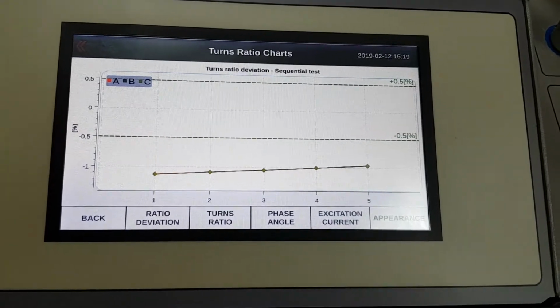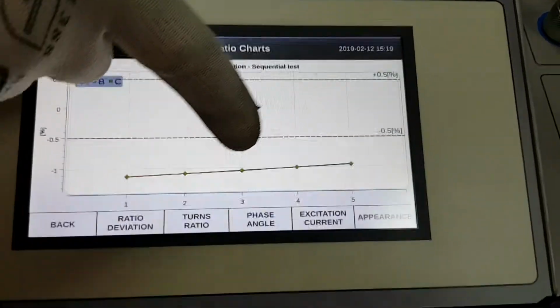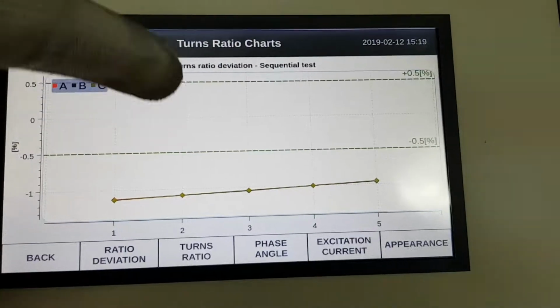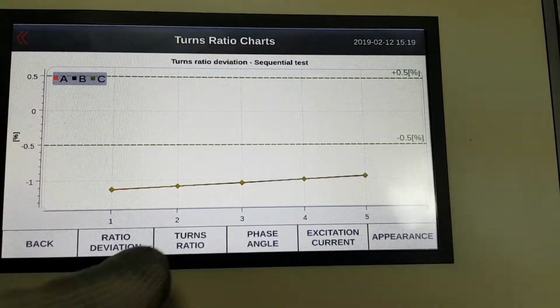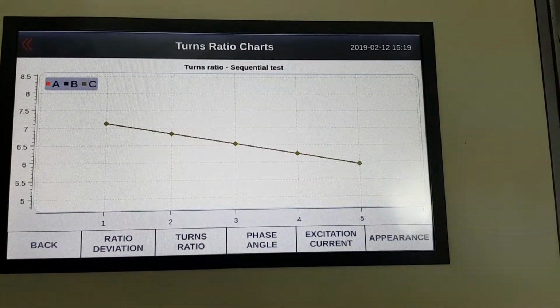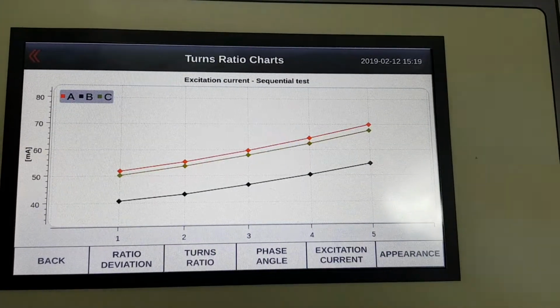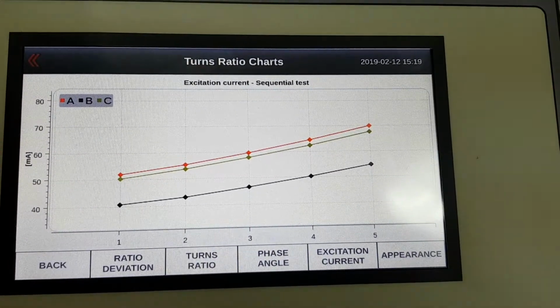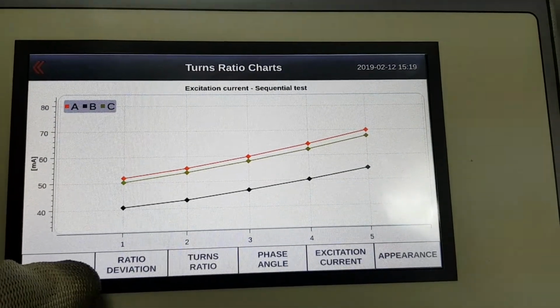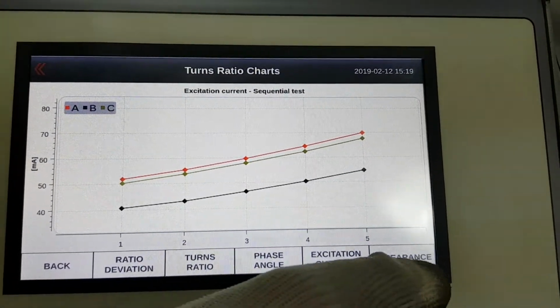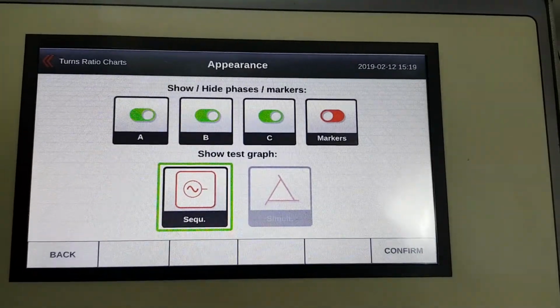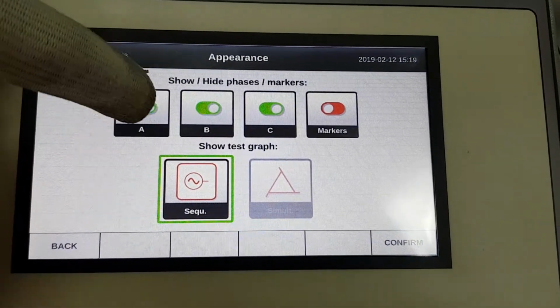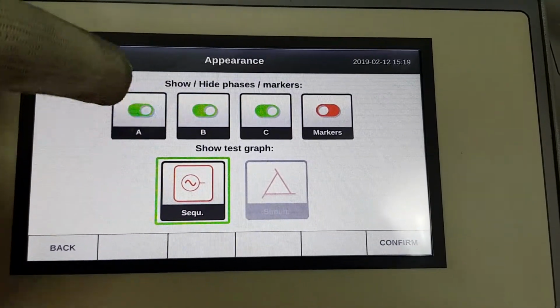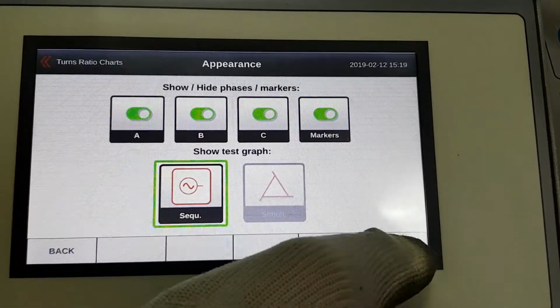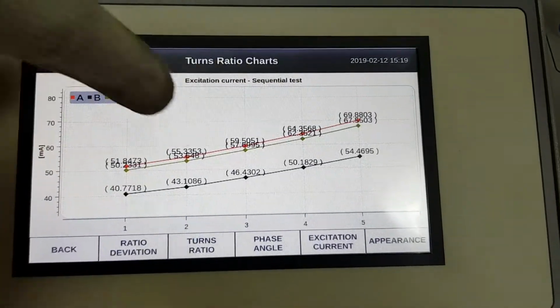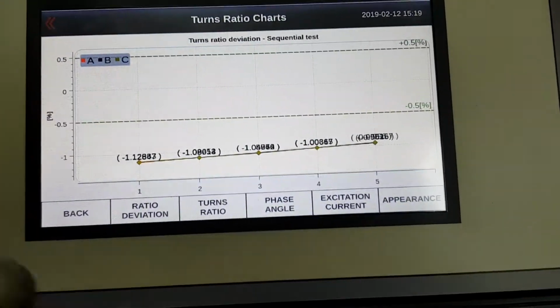By default it's graph of ratio deviation, so we see all 3 phases are outside the green zone, outside of the 0.5% limit. We can also look the turns ratio graph, the phase angle graph, and the graph of excitation currents. And of course in the appearance customize, we can deselect phases. We can show all 3 phases. We can show also the markers, which will show us the exact values on the graph. So we can see here.